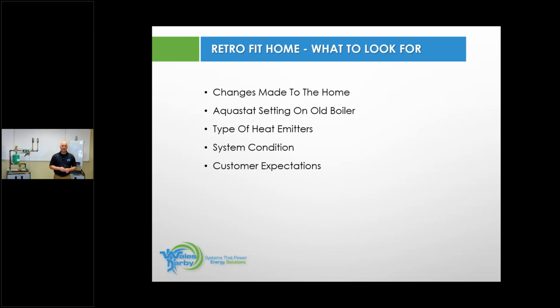Before you remove the old boiler, especially if it's an old cast iron boiler, always look at the aquastat setting on the boiler, the temperature setting on the aquastat off the old boiler. And that's important to know because if that's set at 200 degrees or maybe a little bit above 200 degrees, that is critically important because there are condensing products out there that really may max out at 176 degrees. So if you needed 200 degree water to satisfy the load within that home, 176 is not going to get it done, and you're going to be underheating that home. And then if you hook outdoor reset up to it, you're really going to be underheating that home, basically the life of the boiler.